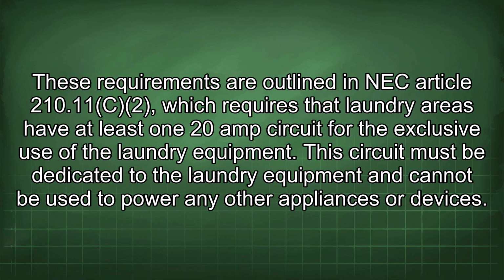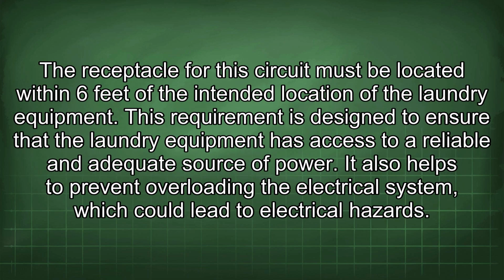These requirements are outlined in NEC Article 210.11c2, which requires that laundry areas have at least one 20-amp circuit for the exclusive use of the laundry equipment. This circuit must be dedicated to the laundry equipment and cannot be used to power any other appliances or devices. The receptacle for the circuit must be located within 6 feet of the intended location of the laundry equipment. This requirement is designed to ensure that the laundry equipment has access to a reliable and adequate source of power. It also helps to prevent overloading the electrical system, which could lead to electrical hazards.